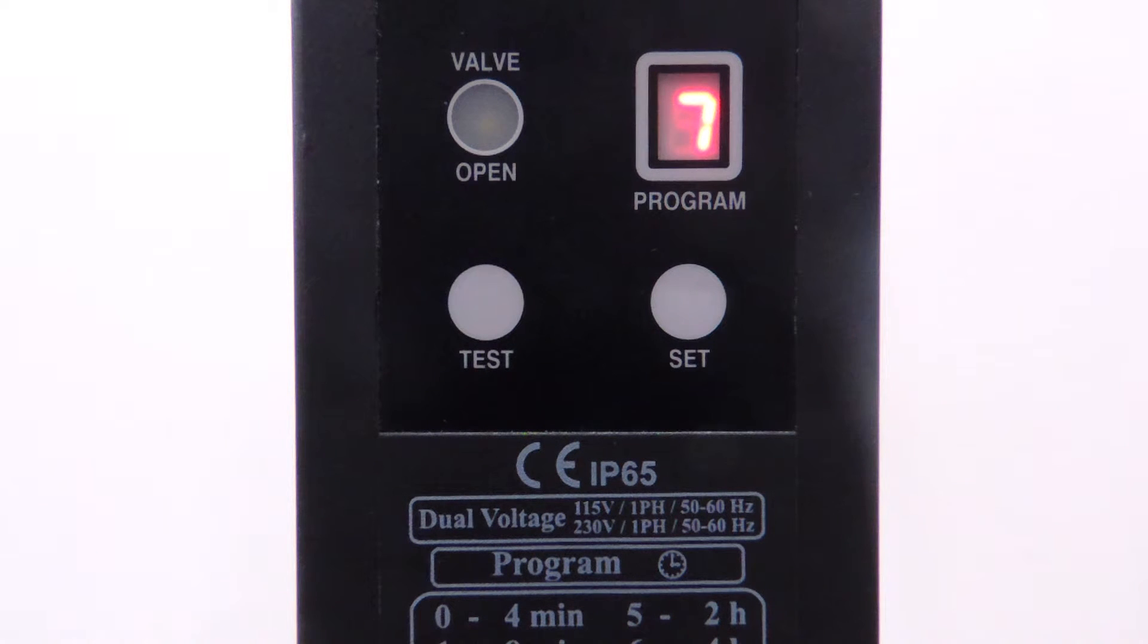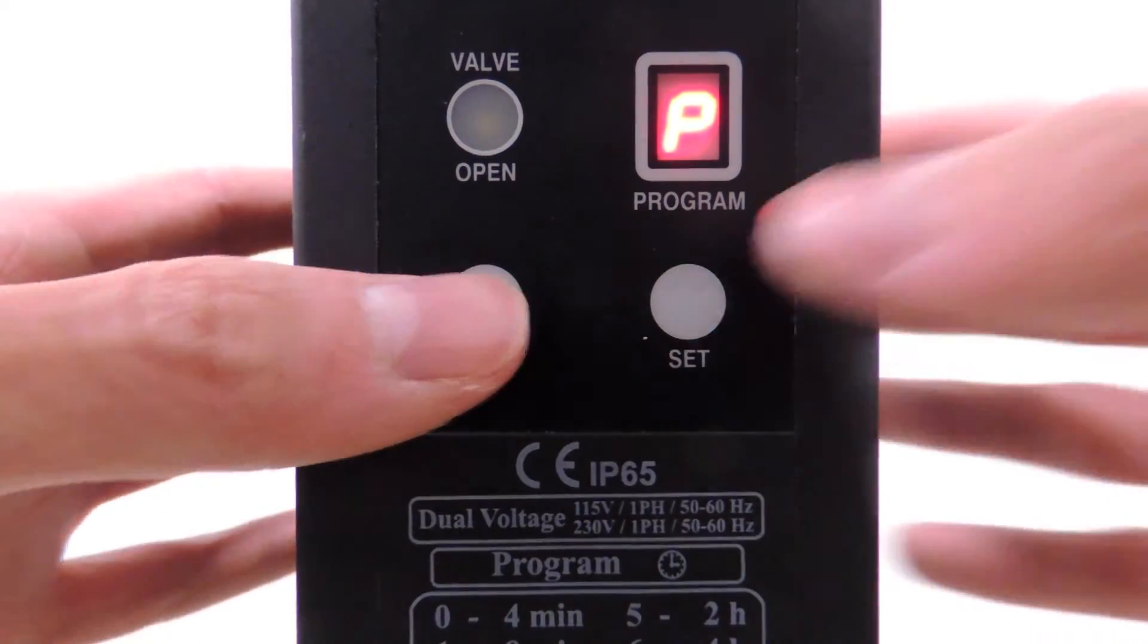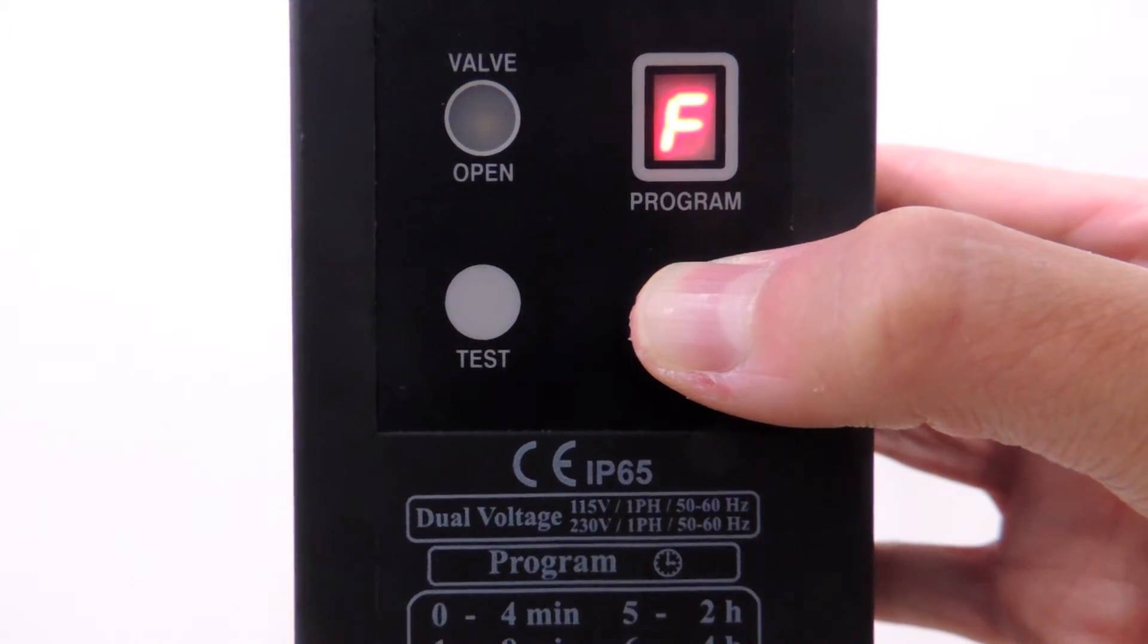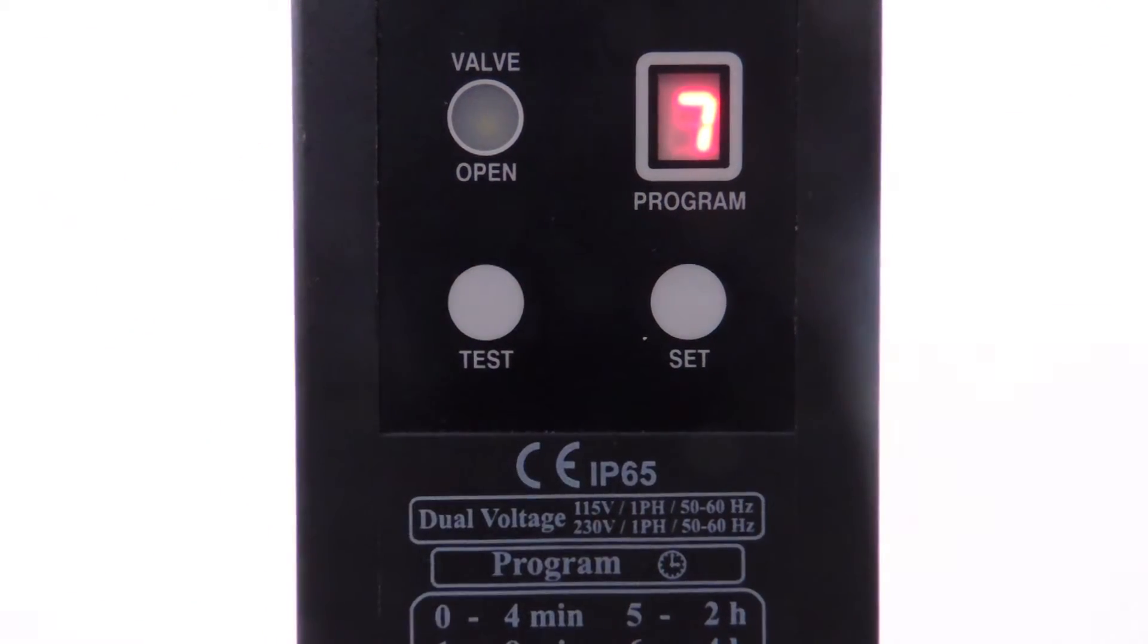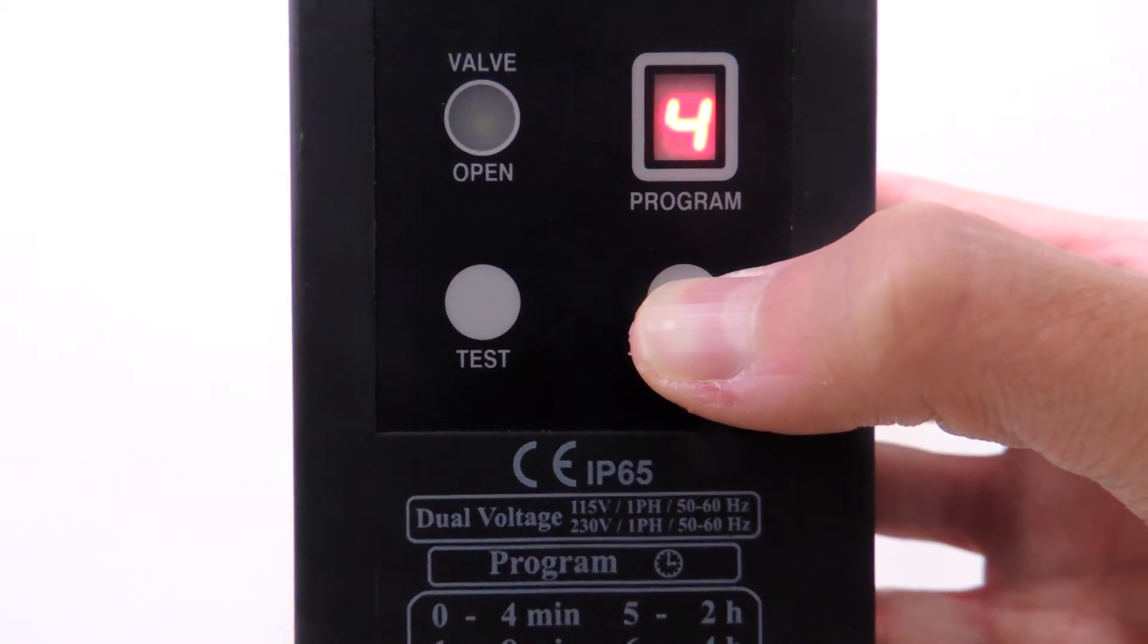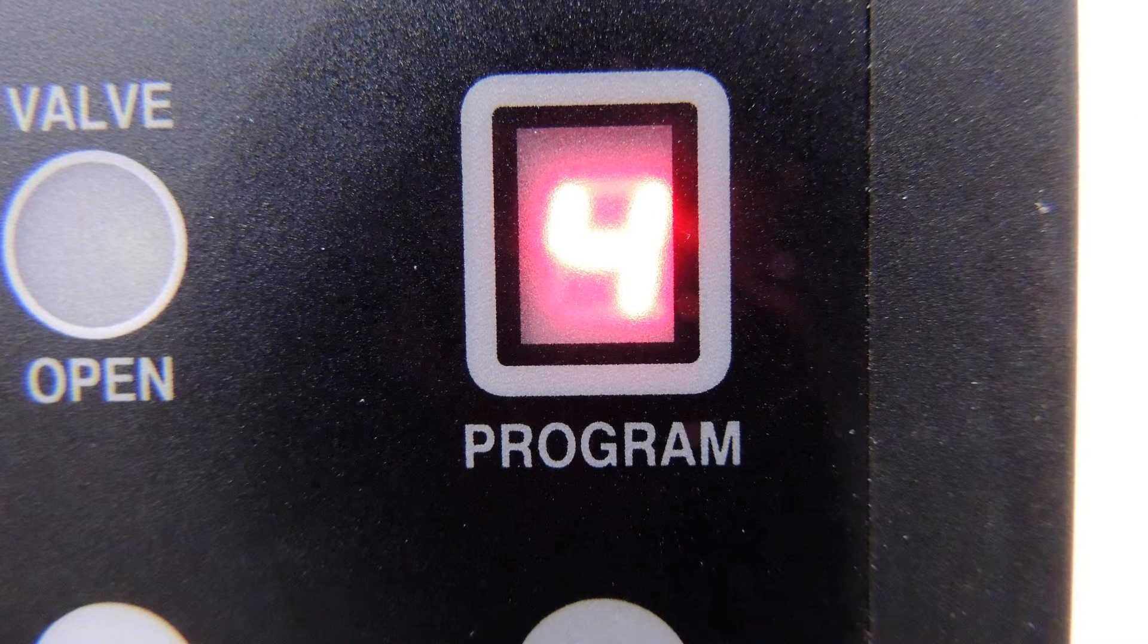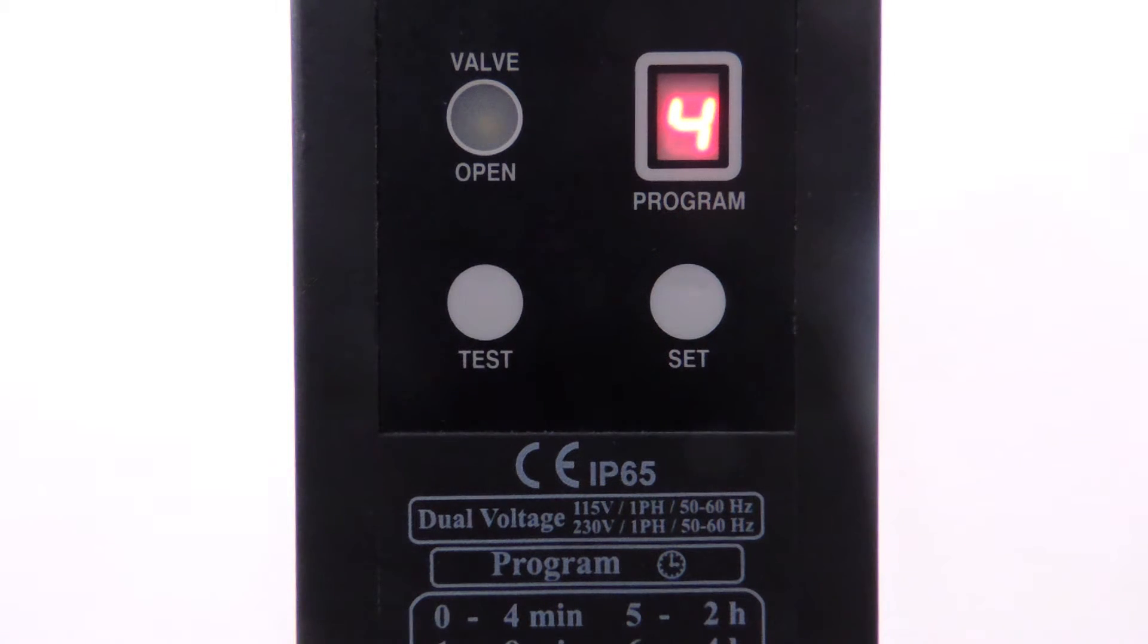To access the purge duration settings, we press Set and Test at the same time. We're going to press Set until setting F is selected, and then press Test to confirm. Then we press Set until setting 4 is selected to choose it as our purge frequency. With F and 4 as our settings, the valve is finished programming to purge for 30 seconds every hour.